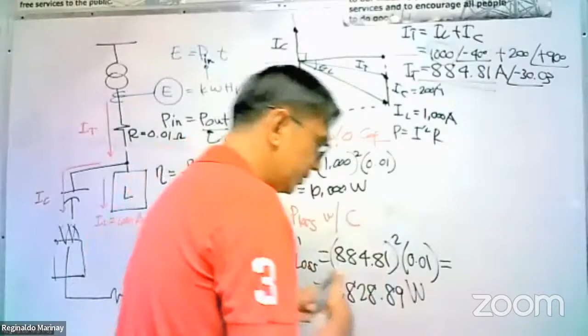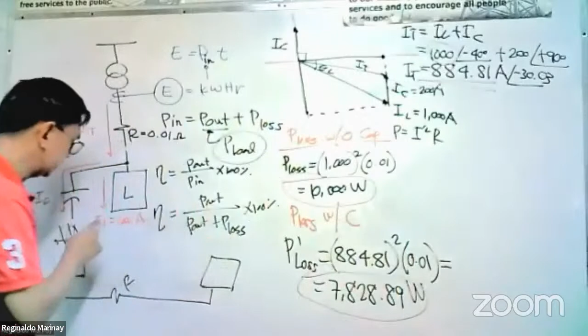That's more than 2,000 watts saving. You see, you reduce the power loss. Actually, power factor correction is loss reduction, it's a way of power loss reduction. It's not actually reducing the load current or load power, no, that is constant here. What is being reduced is the loss on the line.